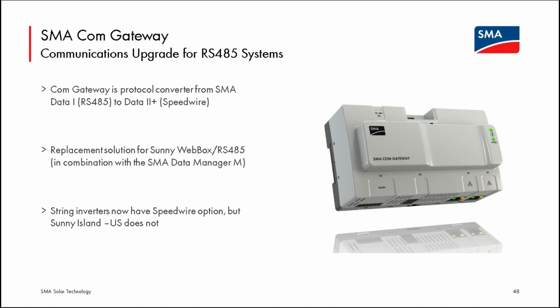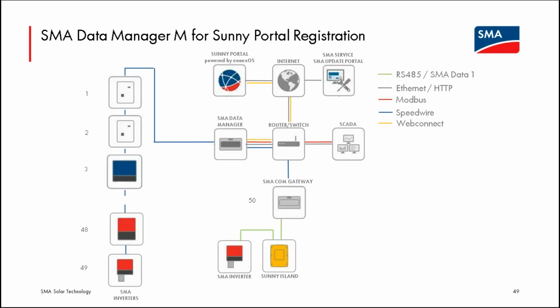The COM gateway shown in this picture is that translator. Unfortunately, and it can gather data from RS-485 SMA devices as well as SpeedWire, the Ethernet-based devices, the COM gateway cannot register directly to the Sunny Portal. So right now, it's slightly painful to send data to SMA Sunny Portal. You can see in this diagram, I have the COM gateway at the lower center, and to the top left of that is a device called the SMA Data Manager. That is the device that can register these devices to SMA Sunny Portal.